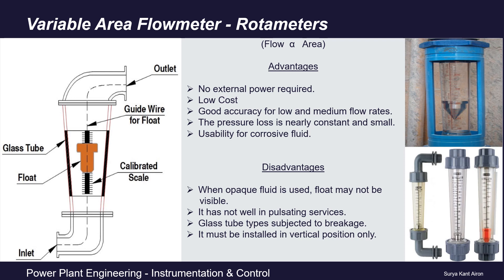The best thing about rotameters is that they do not require any external power supply — all other flow meters need an external power source. They are not too costly, carry good accuracy for low and medium flow rates, have nearly constant and small pressure loss, and can be used for corrosive fluids as well. Disadvantages include that they must be installed only in a vertical position since they work against gravity, and if the fluid is opaque, the float may not be visible.